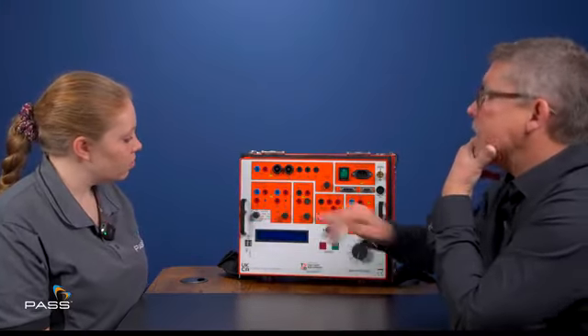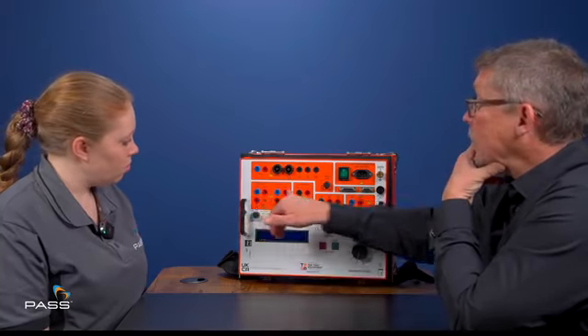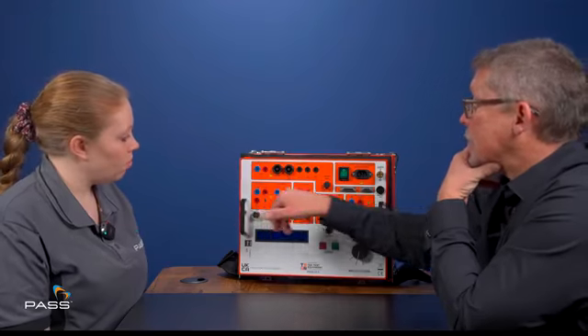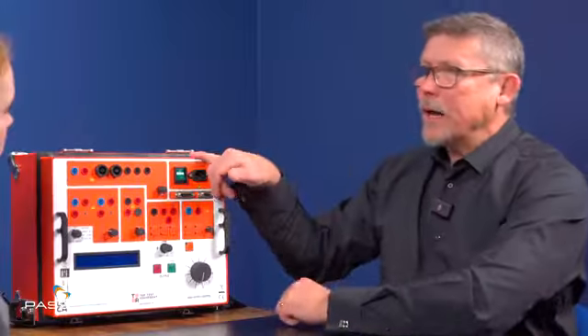But these auto reclosers need to be tested. And what you'll find is, especially if they haven't been operated for some time, they can be quite sluggish on the first couple. So the way that we test it is we've built in here the ability to test these auto reclosers. And if we reverse these, so this one is operated first, the unit is automatically alerted to the fact that it wants to test multiple auto recloser operations. And that allows us then to do open, close, open, close, open, close. And that will actually then graph the results using the CSV file from there. We can actually take the results out, graph them out with the start, stop, and effectively we can interrogate an auto recloser. Again, this is one of the features on this unit I think is pretty unique.